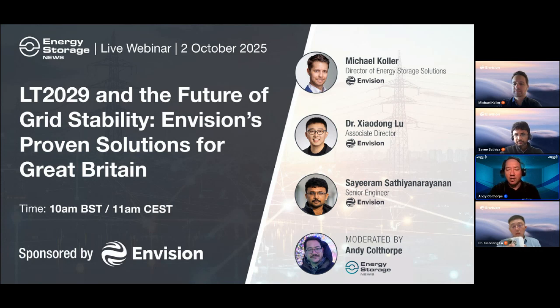Yes, sorry about that. So, a question from Robert. We talked about the competition with synchronous condensers, and the competing applications potentially, and then we obviously have this existing paradigm of the grid in that, as Robert points out, rotating machines supply instantaneous inertia support. And I'm not sure how true this is, but Robert posits that with battery storage and software, there will be a delay, first to detect the issue and then to respond. How long, and what is the effect of this delay? So it's essentially, how closely can grid forming resources mimic the roles played by those traditional thermal power generators? Xiaodong, do you want to go first on this?